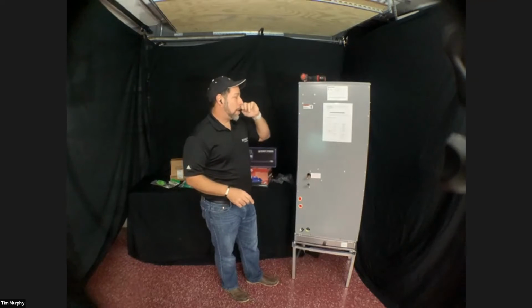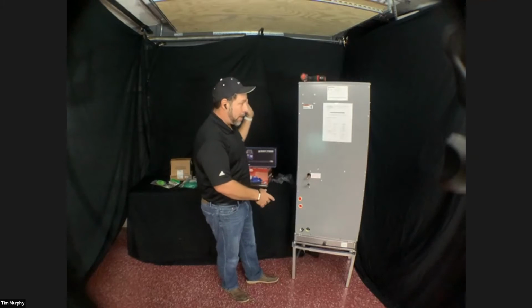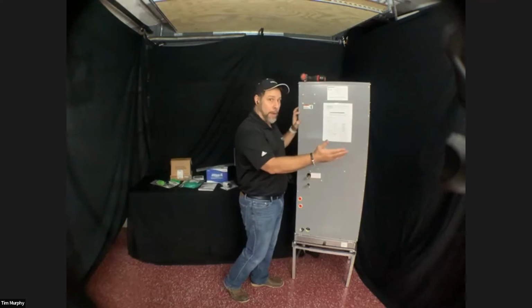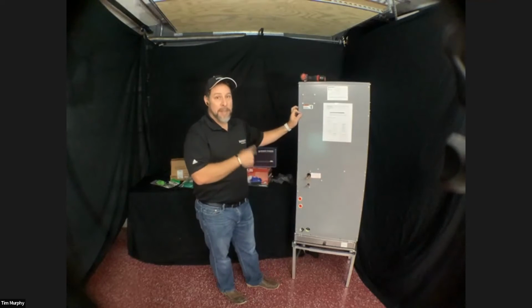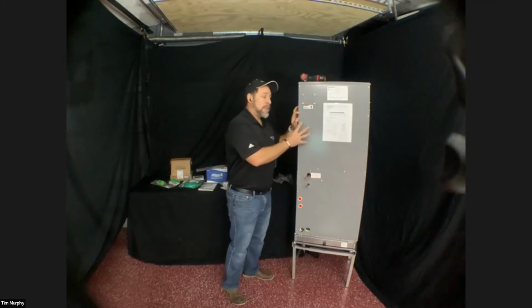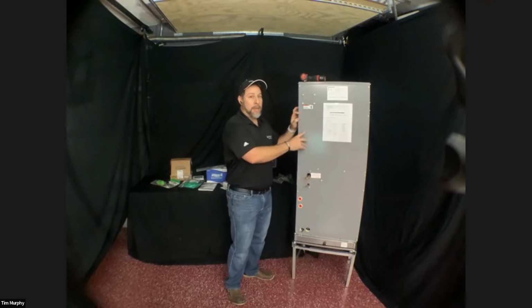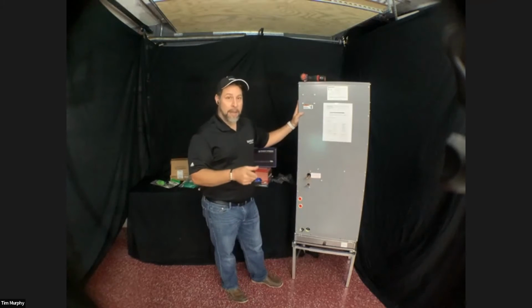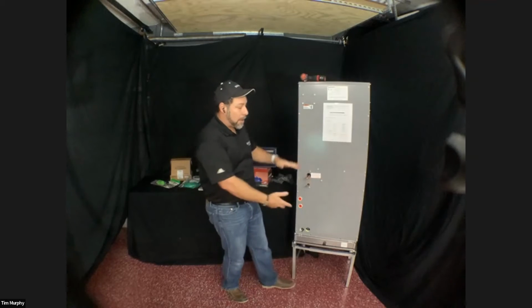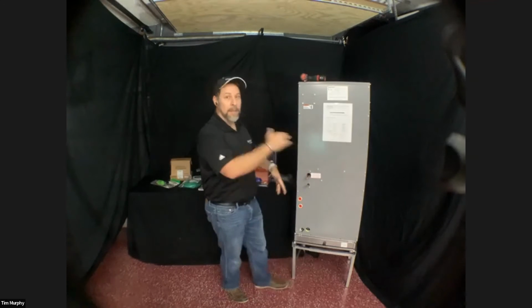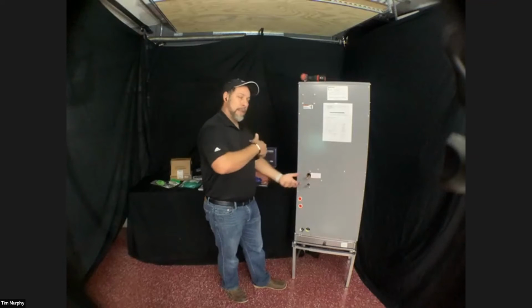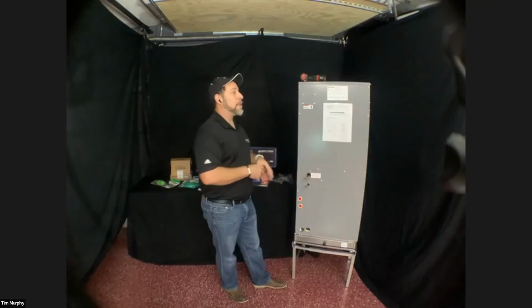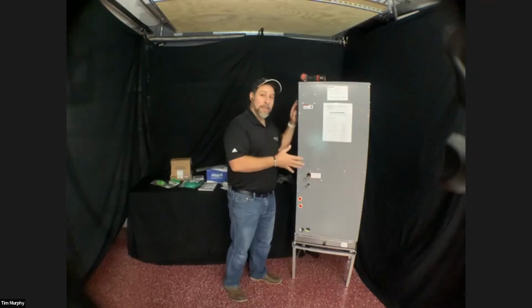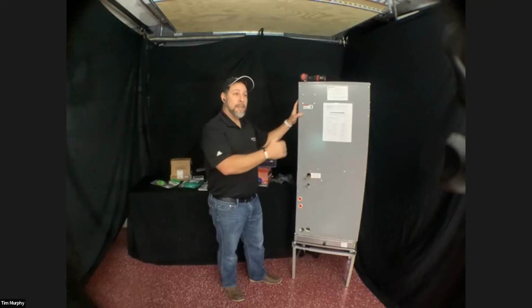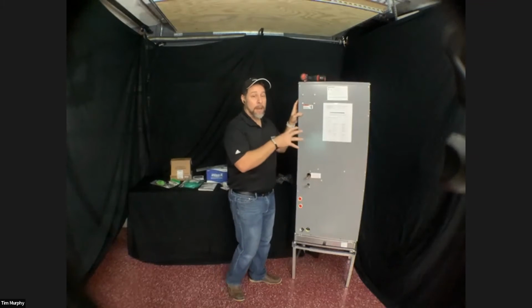Another thing that we want to talk about is this system is a left-hand. It's set up for a left-hand flow. It can be converted to a right-hand flow. It can also be converted to a downflow. If you are going to install this system in a downflow application, you will need to purchase an additional downflow installation kit, which is going to come with brackets, and it's going to allow you to basically flip the coil, and then you'll just take the system and turn it upside down. So if you're doing a downflow application and you're calling your sales consultant, make sure that you let them know, hey, listen, this is downflow. I need that downflow conversion kit.